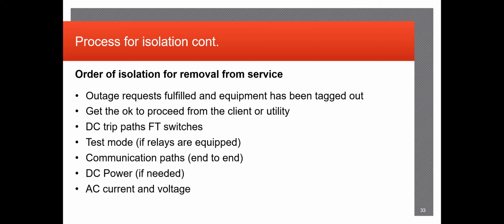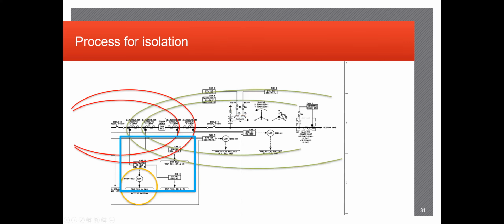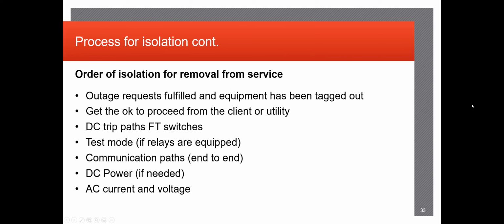Pretty much what I mean is if you just shut off the relay, like I said, it wouldn't only open up this breaker, but there may be a lockout associated with it that could open up another bunch of breakers and maybe even shut down the whole site itself, which is a big no-no. So our job is to identify the order of operations for isolating the relays themselves to avoid any stuff like that. And it actually does apply to lockout relays themselves as well.